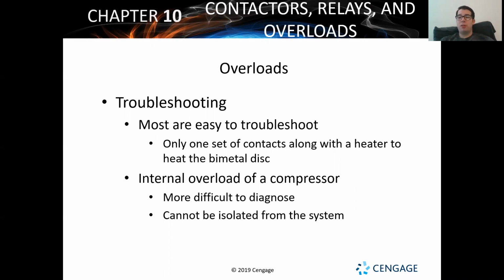He's like, all right, where's the open between start and com? Okay, well, give it a minute. How long has it been since that thing's been off? Oh, I don't know, 30 seconds. Dude, no, give it like 5 minutes at least. And that's all he told me. I gave it 5 minutes, and all of a sudden there's not an open winding anymore. Wonder how that happened. Did the motor magically repair itself? No, it overheated and then it cooled itself off.